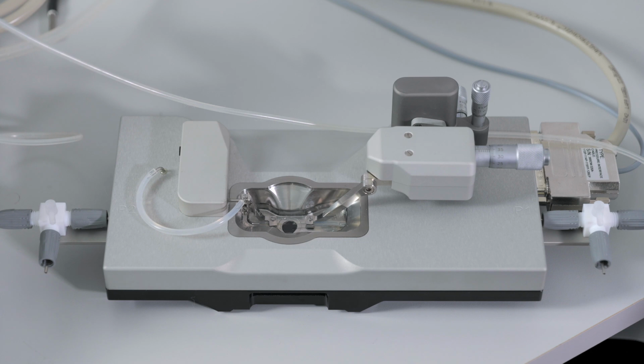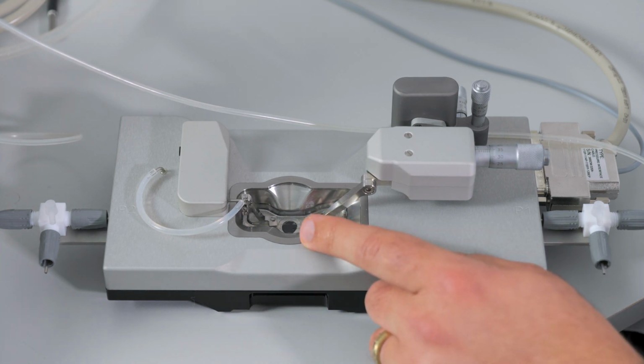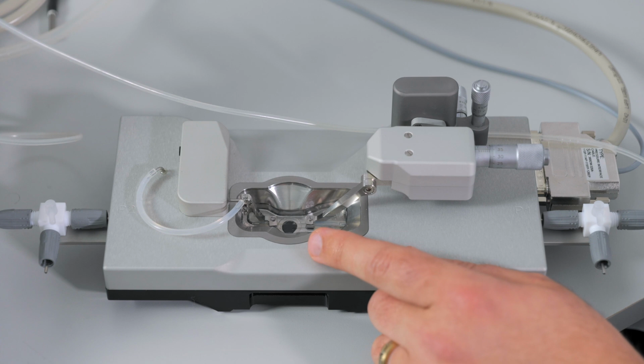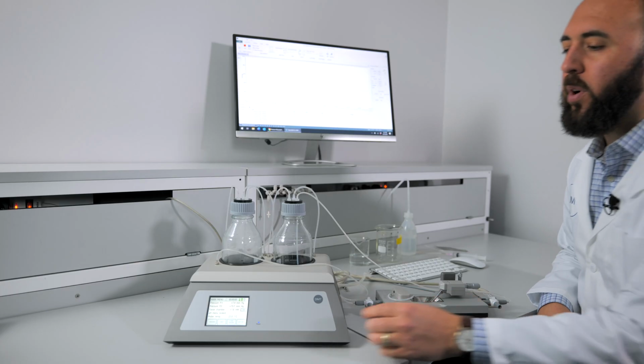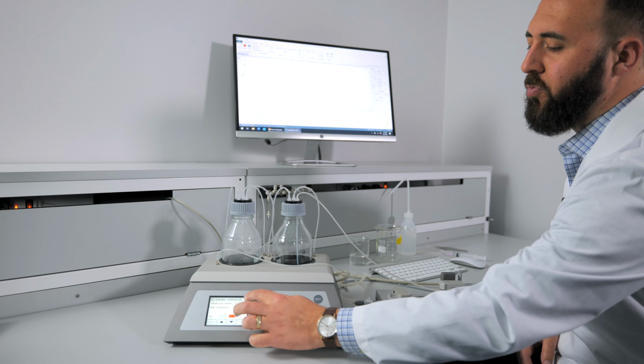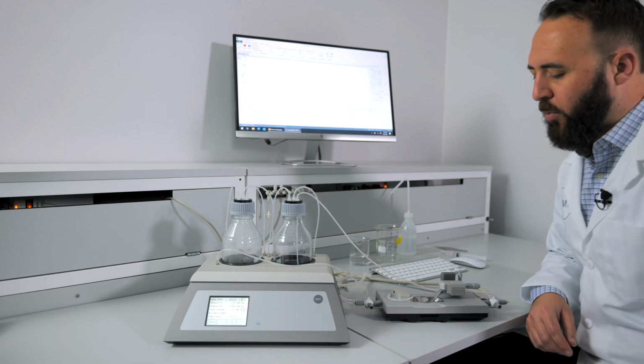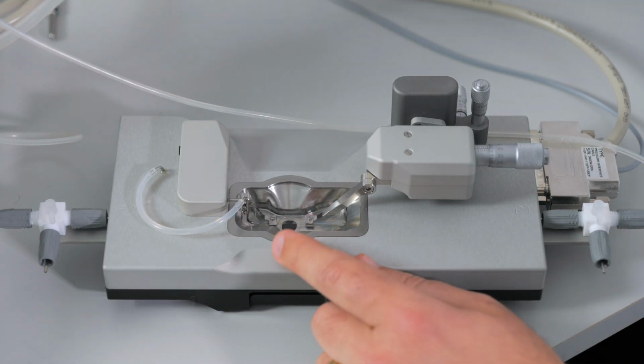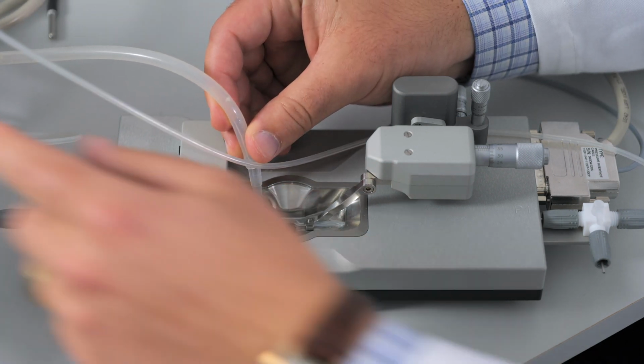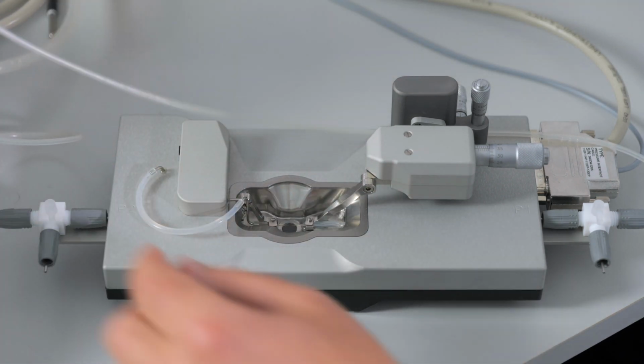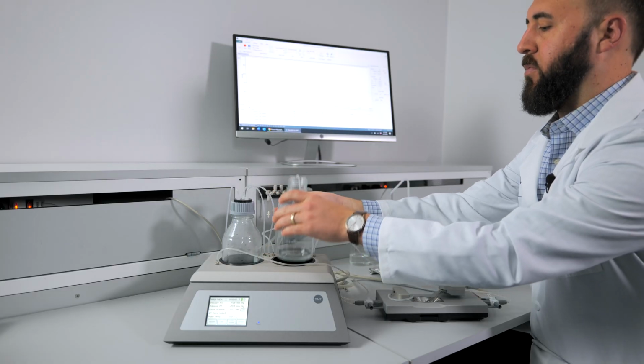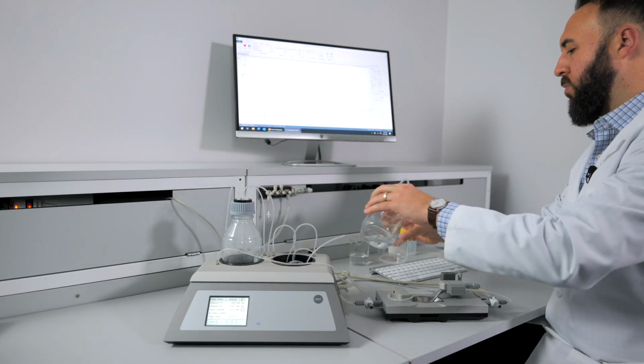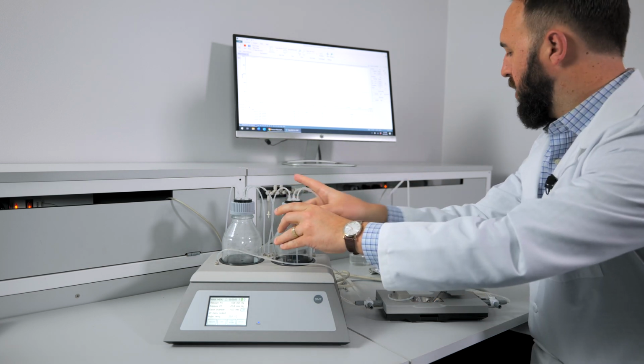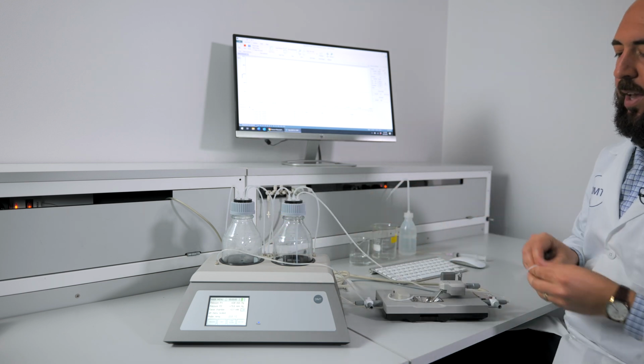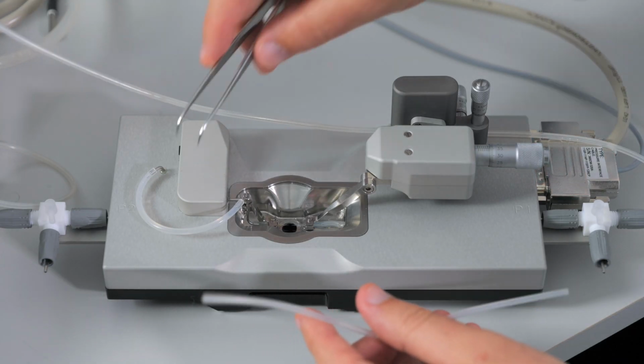At the conclusion of your experiment, you should remove the vessel and the sutures from the chamber, and you should turn off heat using either the software or the interface. You can then remove the buffer from your chamber as well as the P1 bottle on the interface. Secure the bottle cap and place the calibration shunt on the chamber.